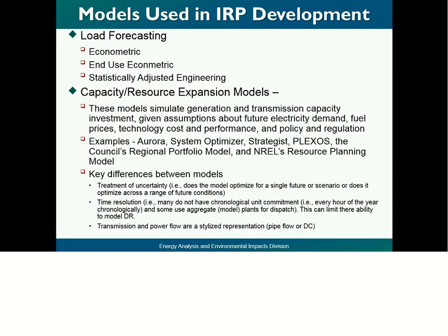And they're what's called agent-based. That is, they make decisions like people do as the future unfolds. And they can decide when to build a resource as the future unfolds, as opposed to, I will build it in 2018. Or I'll be ready to build it in 2018, but if loads don't grow, I'll push it off to 2019 or 2020. If loads do grow a little faster, I will have to do something to respond to that. And if I test enough futures, I'll have some idea of the probability that that will be the right date to build.